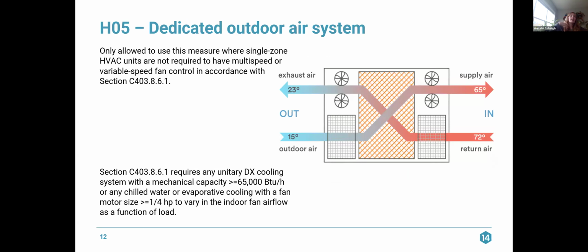The next credit section is H05 dedicated outdoor air system. So this is more complex than what we were used to under the 2021 IECC. And there are quite a few additional requirements. So just to begin with, you are only allowed to use this measure where single zone HVAC units are not required to have multi-speed or variable speed fan control in accordance with section C403.8.6.1.